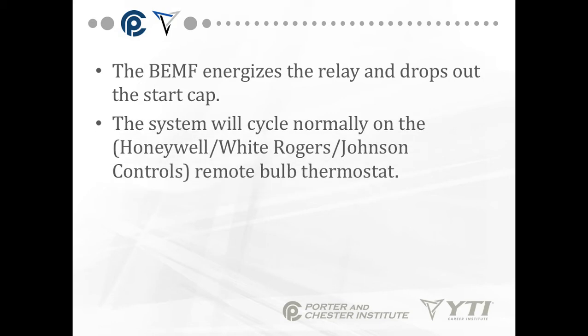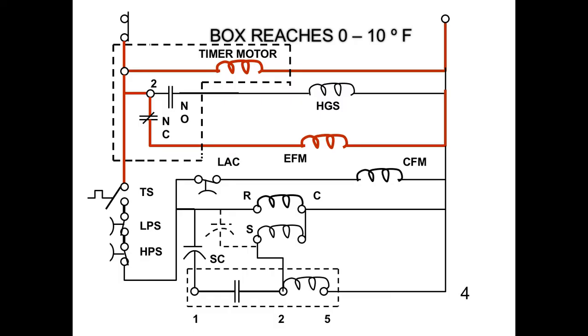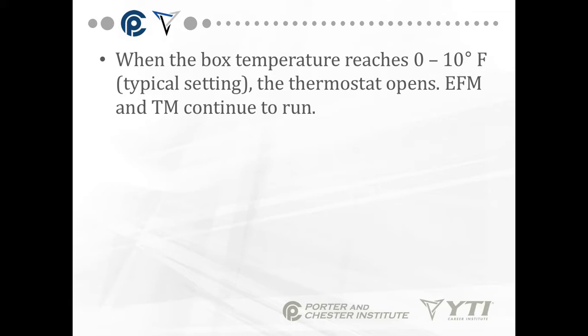So the back EMF energizes the relay and drops out the start cap. The system will cycle normally on the remote bulb thermostat, which is the TS over on the left side. Now the box temperature reaches 0, 10 degrees Fahrenheit, depending on what this is set at. The compressor, condenser fan, all drops out of the circuit. Now because it's a commercial box, it's a commercial system, that evaporator fan is going to continue to run. What that does is prevent hot spots in the cooling system. I don't want to have warm spots, I want it to be a uniform temperature. And how we do that is by keeping the evaporator fan running.